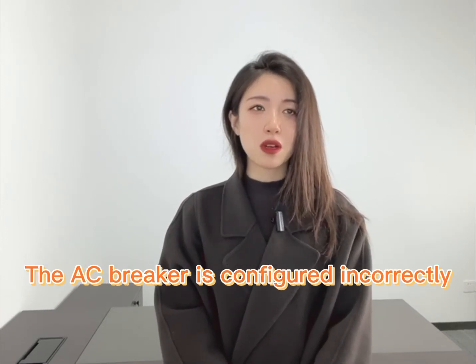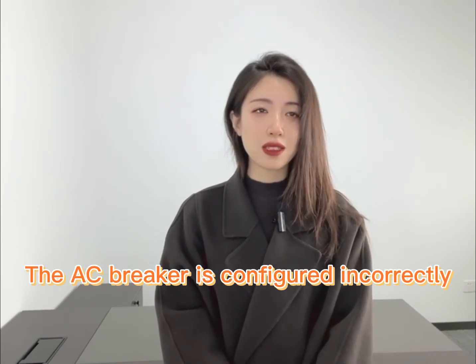The AC breaker is configured incorrectly. In addition to the above two issues, when we select an appropriate AC breaker with reference to AS3008, we also need to make sure the size of the AC breaker is less than the maximum current carried by the cable in the installation environment, and the maximum carrying current of the AC breaker must be greater than the maximum AC current of the inverters by more than 10%.